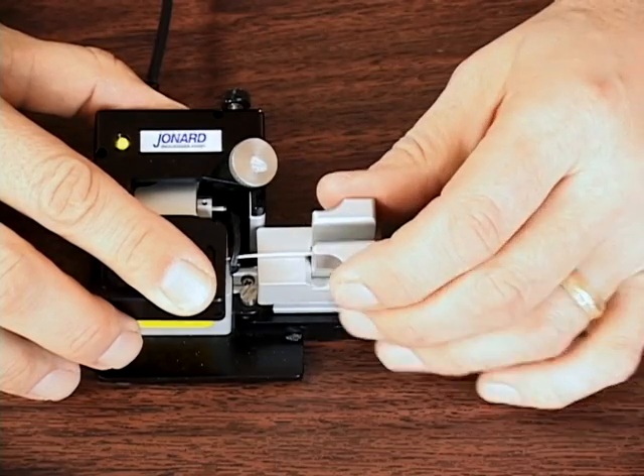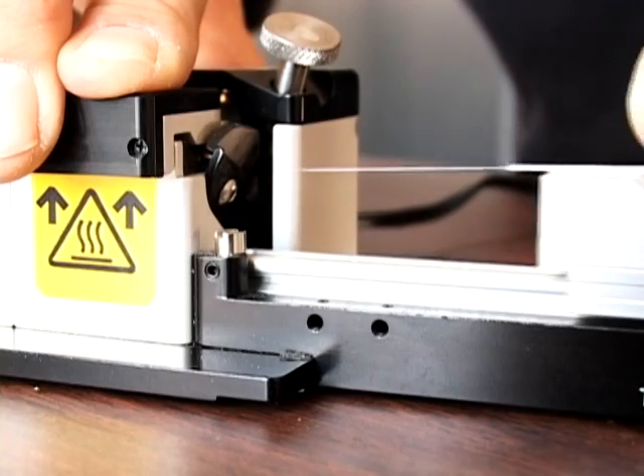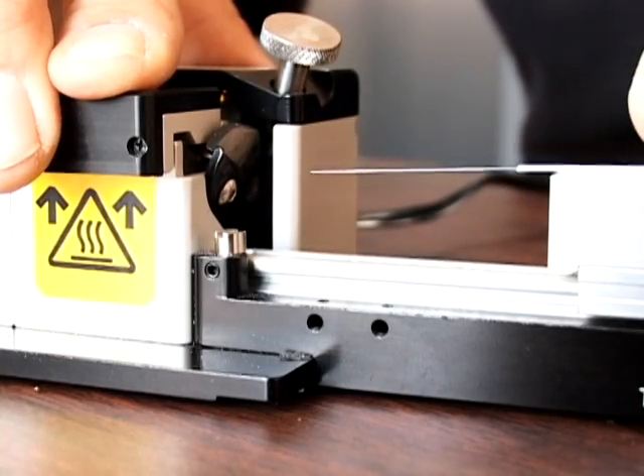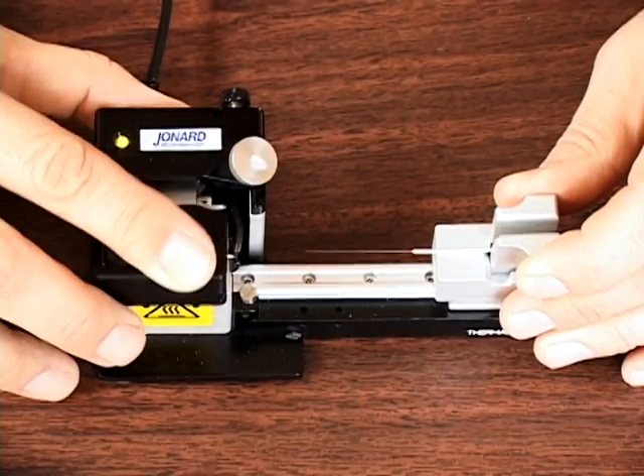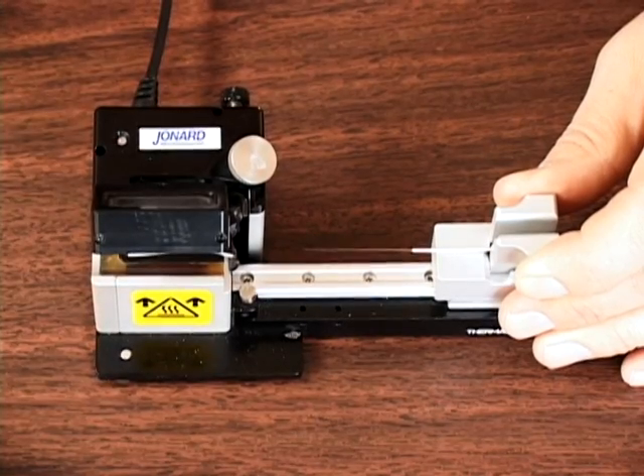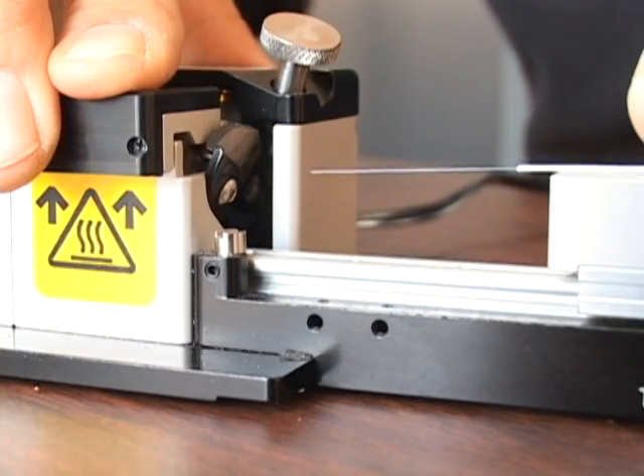Continue to hold the blades closed while you slide the fiber holder and platform away from the heating element. Release the lid and remove the fiber. The fiber is now ready to be cleaned, cleaved, and spliced.